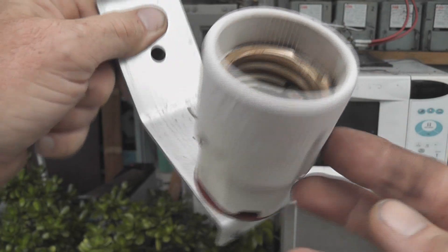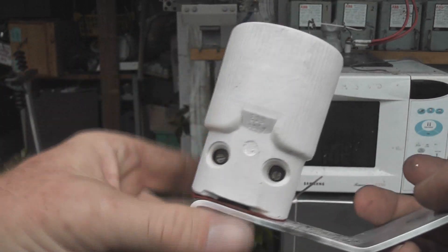So that's why the lead probably blew off. That's worth a try anyway. The fitting has flashed over inside—E40 fitting—so I need to clean that up. I need to put flying leads on there basically. Both leads are blown off, more or less, probably arced up to the aluminum here.